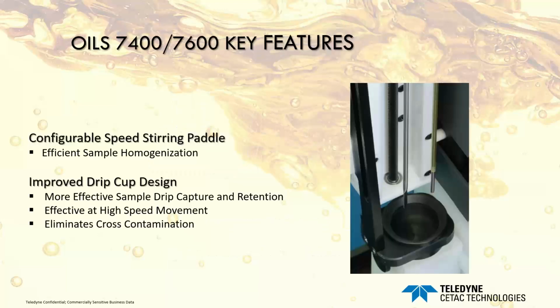And two of the key features for the Oil 7400 and Oil 7600 are the stirring paddle and the drip cup. The configurable speed stirring paddle mixes the sample prior to sample introduction and ensures the best possible results. The drip cup captures drips, preventing them from contaminating other samples. The drip cup mechanism is much improved over our previous designs. There's no switches or springs to wear out. Instead, the cup is actuated by a cam that moves along with the probe and the stir mode. So as the probe and stir move up, the cup swings under them. It is very reliable, and our customers that have been using this love it.